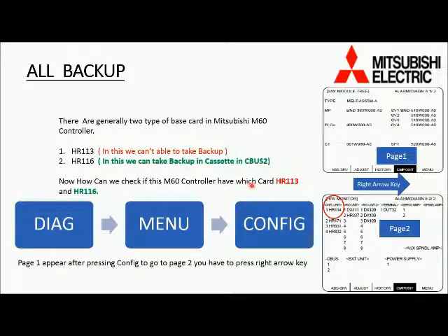Please press Diag on the keyboard, then Menu in the soft key, then Config in the soft key. Then we will come to page 1. For going to page 2, which is the hardware page, we have to press the right arrow key. Then check the red circle — you can find the card name there: HR 113, HR 116, or HR 114.